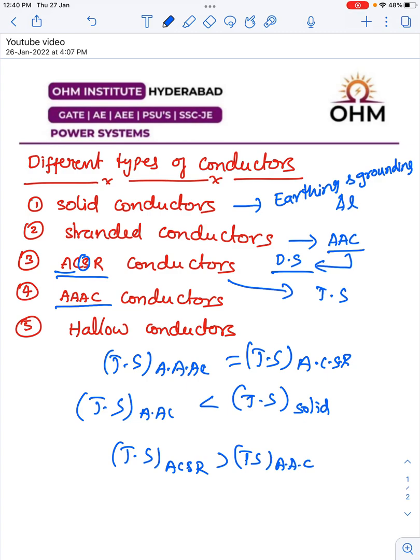For example, in the transmission system, if you want to use lightweight towers, you definitely need lightweight conductors. ACSR conductors are not suitable in that case. Lightweight towers are used especially in hilly areas, where tower erection work is not simple. That is why we try to make towers with lightweight steel, and lightweight conductors like AAAC are required. In the distribution system also, we use AAAC conductors where we need longer spans — especially at railway crossings, road crossings, and river crossings. AAC is not suitable for those longer spans, and ACSR is not suitable because of the lightweight towers used in distribution. So it is better to go for AAAC conductors. Triple AC conductors are used in distribution for longer spans and in transmission where lightweight towers are preferred.